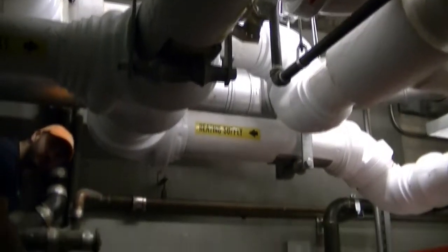Now, in this building, we're a little bit different. We leave the boiler room and then we go through a mixing valve that tempers that water down to go out to your individual heating system for the building. Whether it's, I don't know, is it baseboard, radiators? What do we have in the individual? Fan coil. So we have a mixing valve that tempers down the water going out to the fan coils, and there's another common supply sensor there monitoring that temperature.